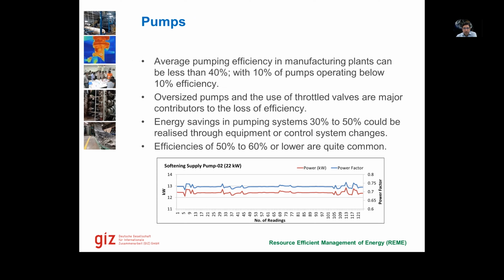Then pumps. On average, if you do an overall analysis of efficiency, we find pumps far less efficient: 40%, 30%, 25%. This one graph at the bottom shows a pump running at a low power factor because it's a large pump and the demand is low. These are the kinds of pumps where we can explore the possibility of installing variable frequency drives, and we can also do a pump efficiency analysis. Even using this MEASUR tool, for example, it allows you to calculate the losses in the pump system. So it calculates different kinds of losses that can be there. So I recommend that you use the MEASUR system for pumps as well.